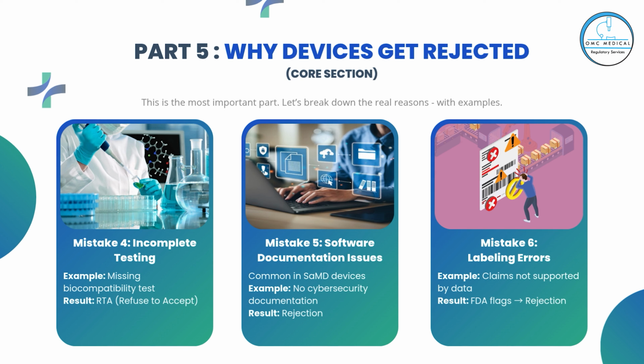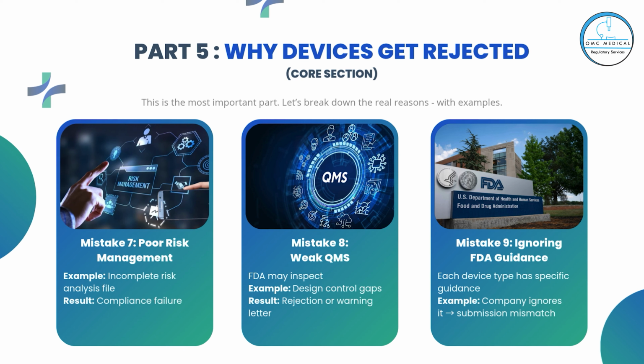Mistake 5. Software documentation issues, common in SaMD devices. Example: no cybersecurity documentation. Result: rejection. Mistake 6. Labeling errors. Example: claims not supported by data. Result: FDA flags it, leads to rejection. Mistake 7. Poor risk management. Example: incomplete risk analysis file. Result: compliance failure. Mistake 8. Weak QMS. FDA may inspect. Example: design control gaps. Result: rejection or warning letter.